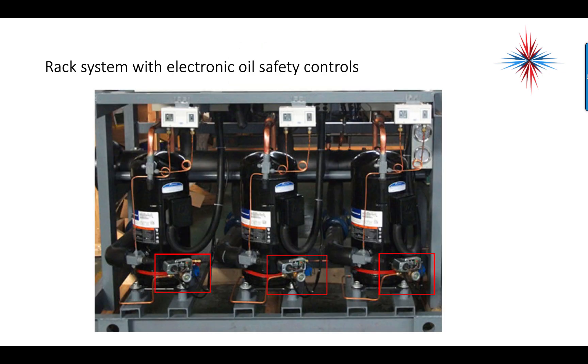Here is a rack system with electronic oil safety controls. We have multiple compressors all wired together. All of them have manual oil pressure differential controls as well as high-low pressure controls, and the oil level safety controls are right there.